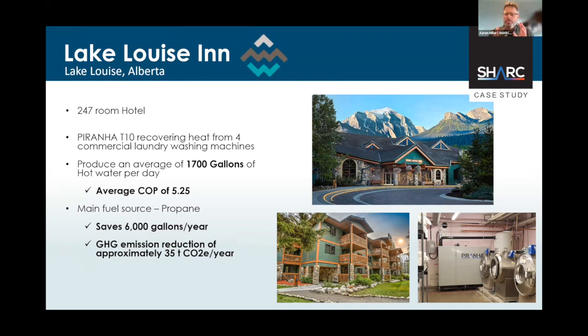So the hotel was looking for energy efficiency opportunities. We shoehorned a piranha into their laundry room—literally shoehorned it in. What we're doing is capturing the wastewater out of these four commercial laundry machines into a tank they already have on site, because laundry machines have to pre-capture it to let the lint fall out. So we pump all that warm water back into our piranha and then fill this tank on the right-hand side with hot water, so that the washing machines, when they cycle up again, are using hot water made from the wastewater coming out of the machines they just ran.